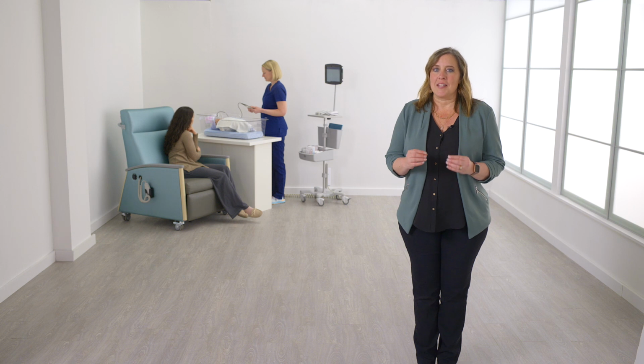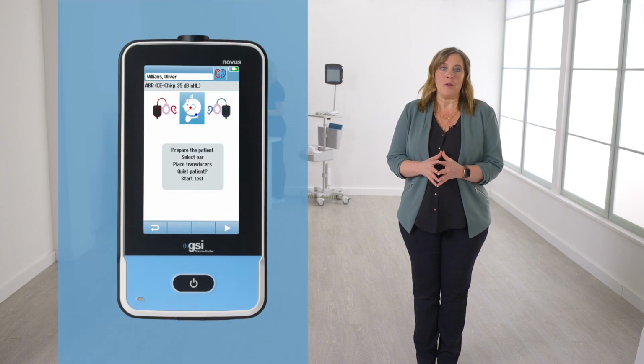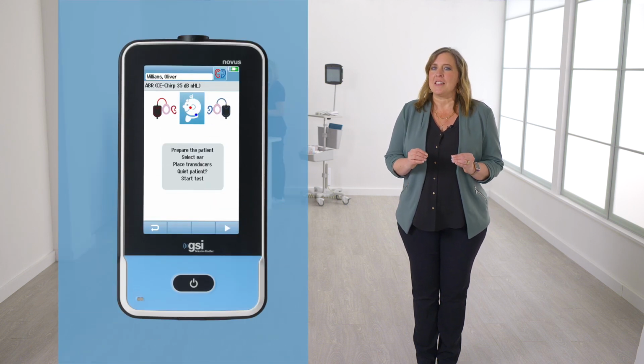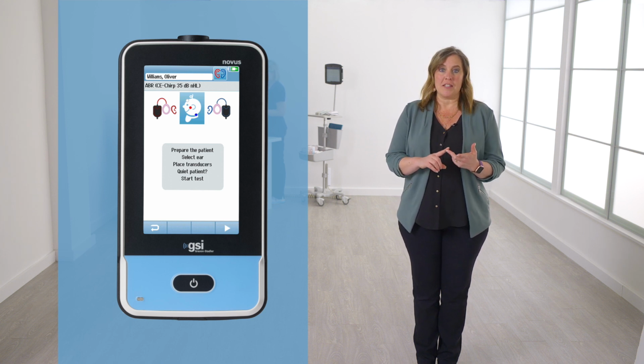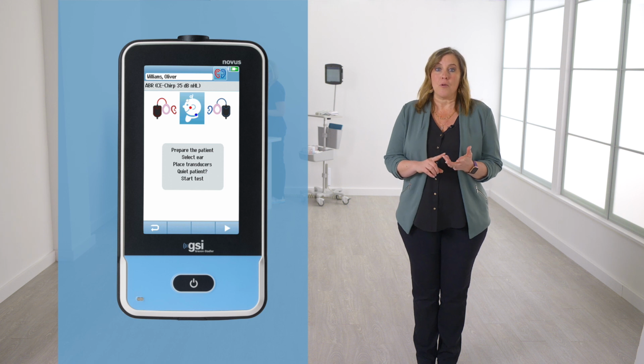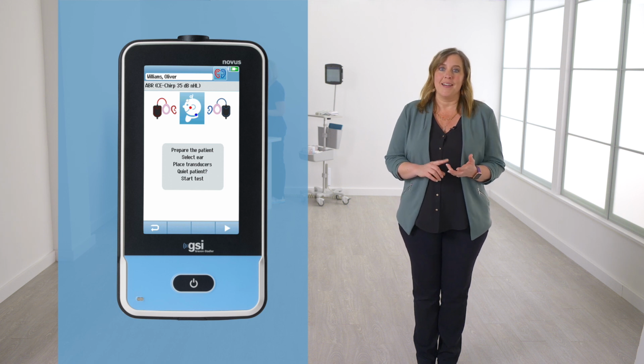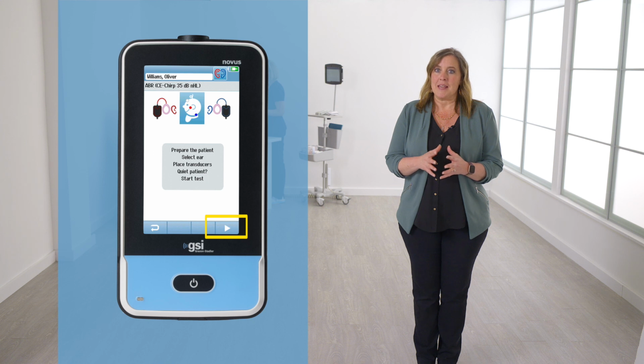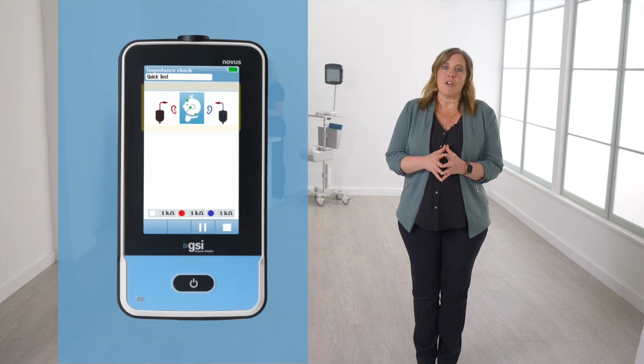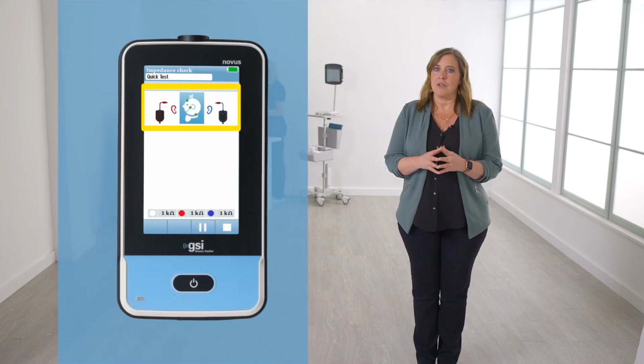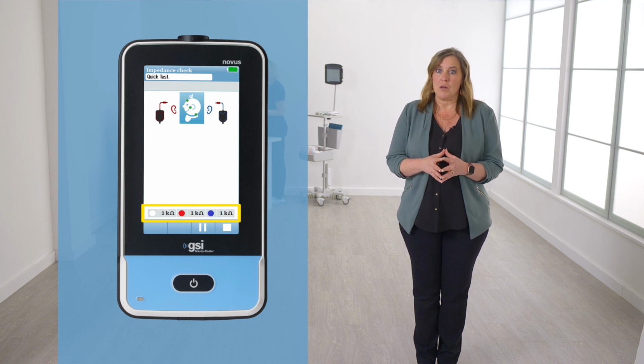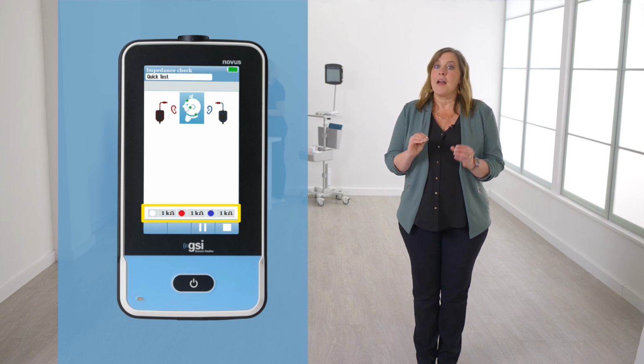Once the patient name is selected, the initial test prep screen will appear. Take a couple of seconds to verify the patient's name, ensure that the transducer icons match the transducers you are using, and that the appropriate ear or ears are selected. Then, press the Start button to begin the impedance check. There's an illustration with a color-coded dot at each electrode site that will turn orange or green. The numerical values at the bottom of the screen will show the actual impedance value for each electrode. The lower the number, the better the impedance and the faster the test.